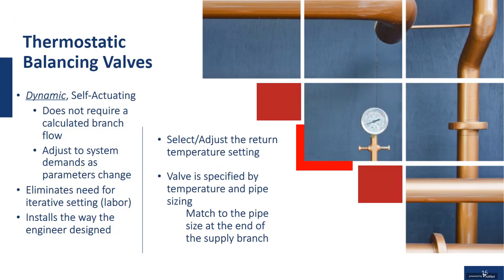So as I said, they're dynamic, they're self-actuated, they don't require any external power as an electric balancing valve would. They're basically opening and closing based on the temperature of the fluid going through them. That's what causes the wax to melt and change its position, so they adjust to system demands as parameters change.